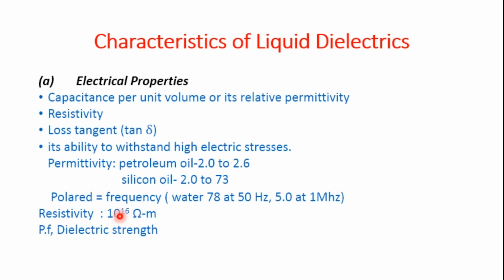The dielectric strength is the most important parameter in the choice of a liquid dielectric for a specific application. It mainly depends upon the atomic and molecular properties of the liquid. However, under practical conditions, it mainly depends upon the material of the electrode, the temperature, the type of voltage applied, and the gas content in the liquid. These factors, together with changes in the molecular property of the liquid, control the breakdown strength and lead to electrical breakdown of the liquid dielectric. So this is subject to the electrical properties.